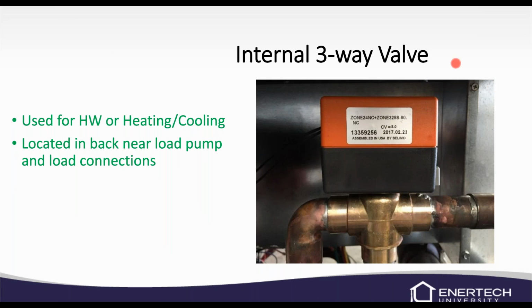This is the internal 3-way valve. This is what shifts from domestic heating or hydronic heating, to domestic hot water heating. Again, it's just a 3-way valve. And you can move it by hand if you need to. If for some reason it were to stick, you could move it by hand. And you can also just replace the head on it, not the whole valve body.